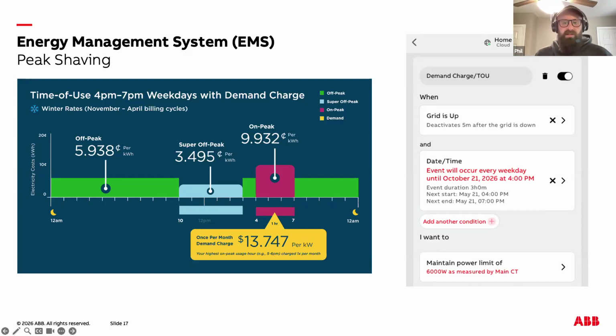The screenshot to the right of the slide is from our ABB ReliaHome app, showing the power limiting feature available within our EMS solutions. So you can see when the grid is up between May 21st and October 20th, Monday through Friday, between the hours of 4 and 7 p.m., I'm setting the system to maintain a low total power limit of 6 kW, and that will prevent excess demand charges and save the consumer money. It's not an overload protection, it's just for the benefit of the end user.